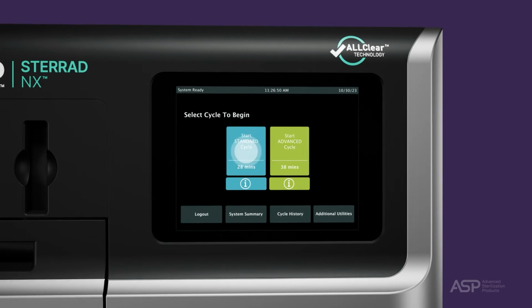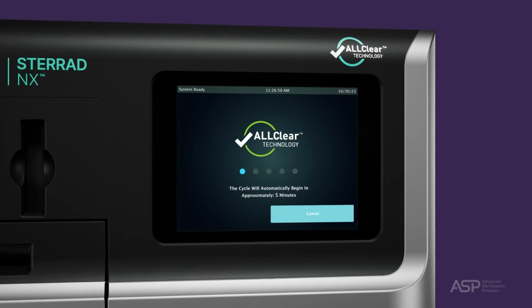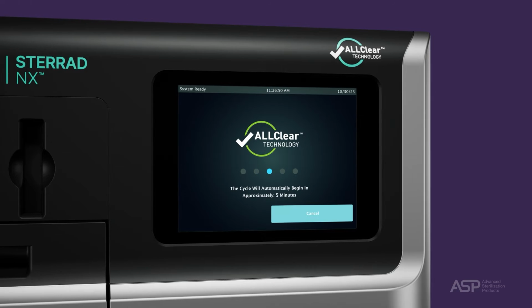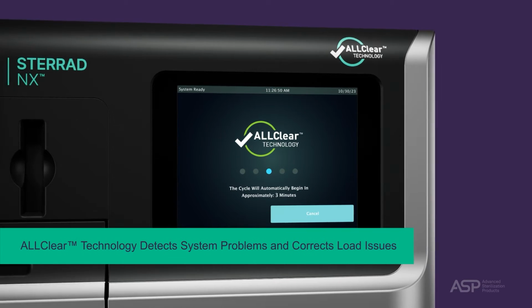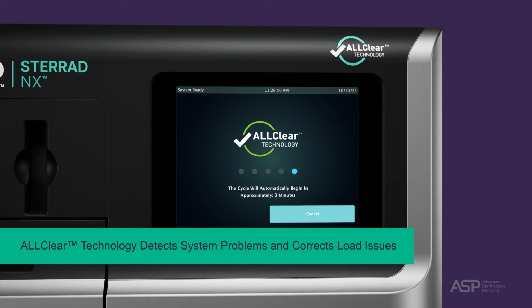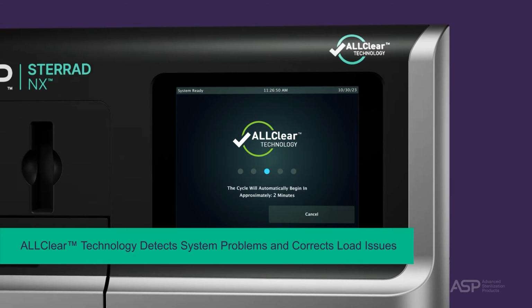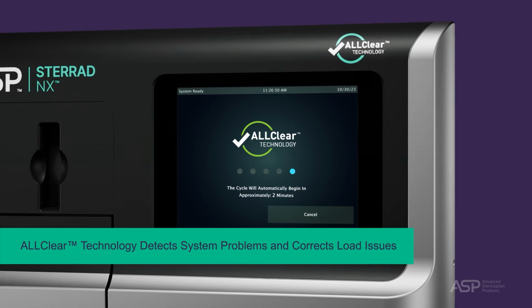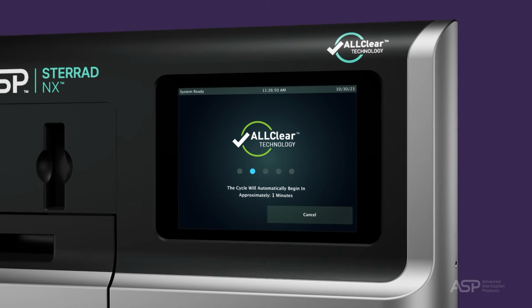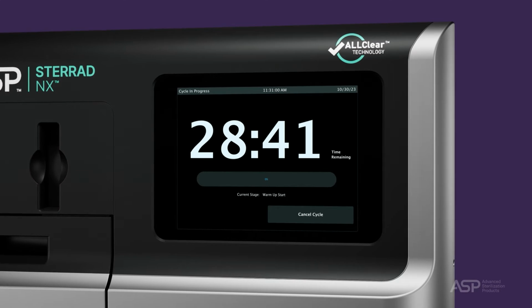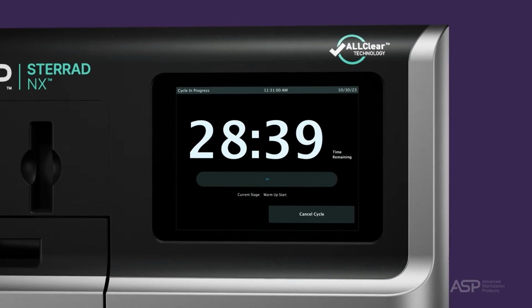Select the desired cycle and press Start Cycle. The ALLClear technology process begins and is displayed on the monitor. This is a load conditioning process that minimizes the number of sterilization cycle cancellations by detecting system problems and correcting load issues. Once the ALLClear technology process completes successfully, the sterilizer starts a countdown clock and begins the sterilization.